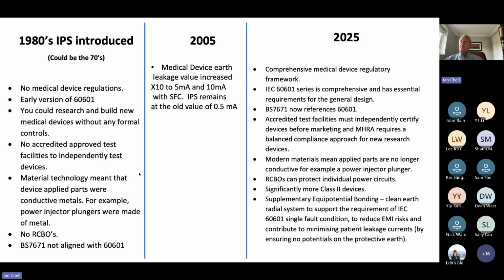We have the radial system to support the requirements of the 60601 single fault condition, to reduce EMI and to contribute to minimizing patient leakage. Now I won't go into the technical side of that too much, but I call it the backward patient leakage: if you had some voltage on the protective earth and it was connected to the patient somehow, then that would leak back through the medical device. So the only real leakage we should get is from the device through to earth, and that is regulated or controlled by the device and clinical engineering. A lot to take in, but these are crucial points.